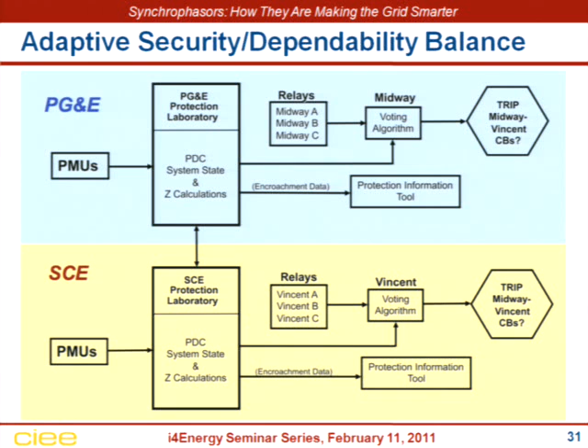But here's where the key PMUs are on the system. We've got Vaca-Dixon, which is just north of here off of 80. This is Tesla, which is that big substation right off of 580 out past Tracy. There's Diablo Canyon, and there's Devers, which is a big major substation in Southern California. Those are the PMUs. Those 4 sets of PMU data are sufficient to feed into this algorithm and have the algorithm say, okay, I know when the system is stressed and when it isn't.